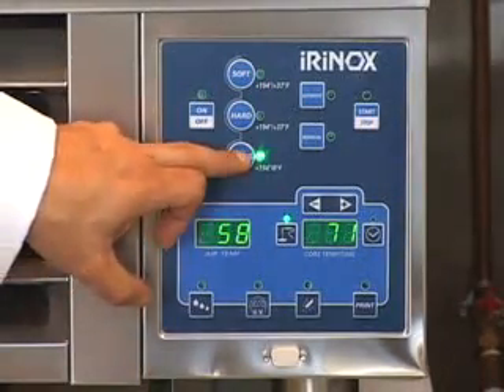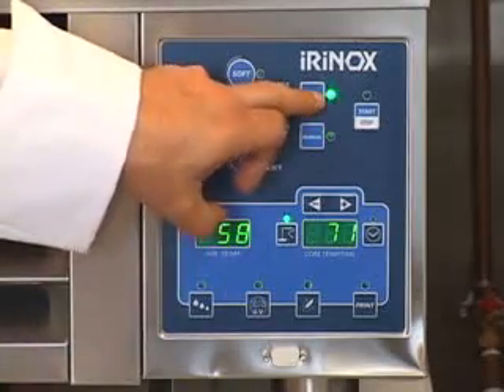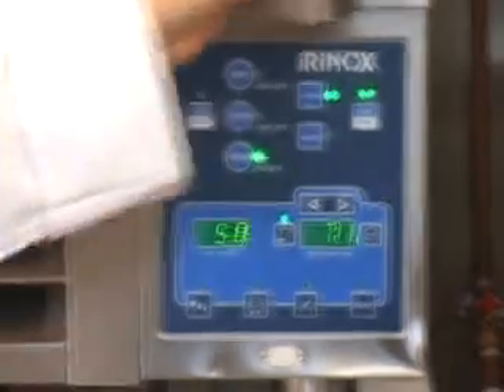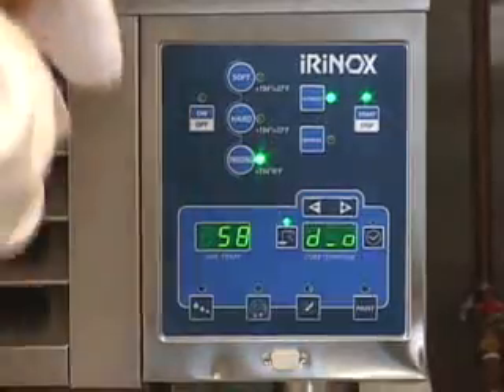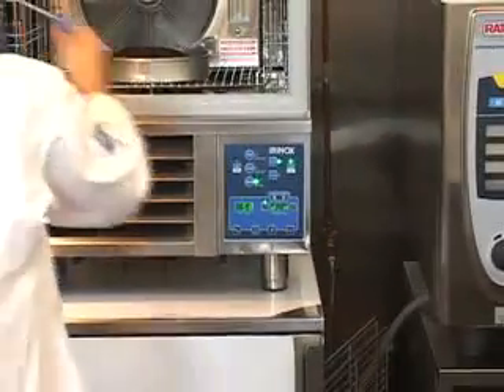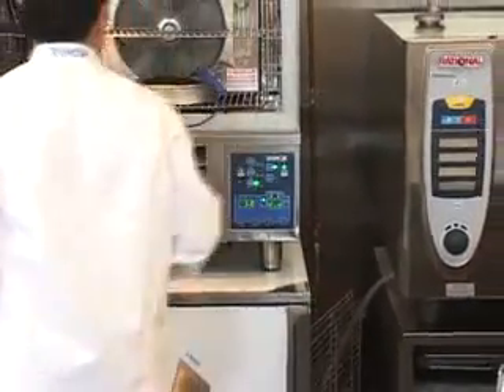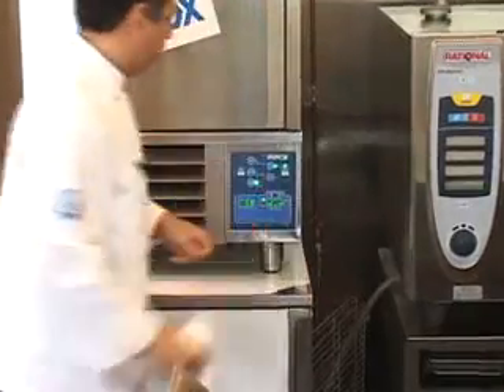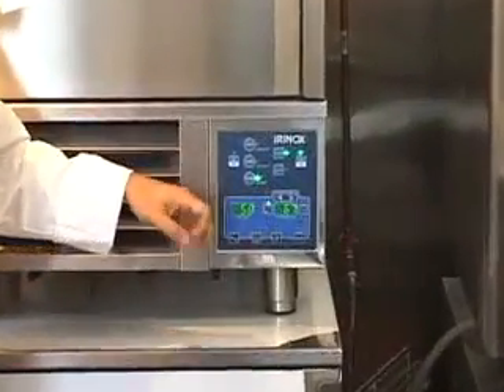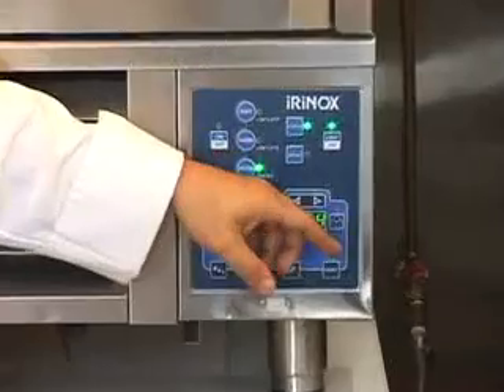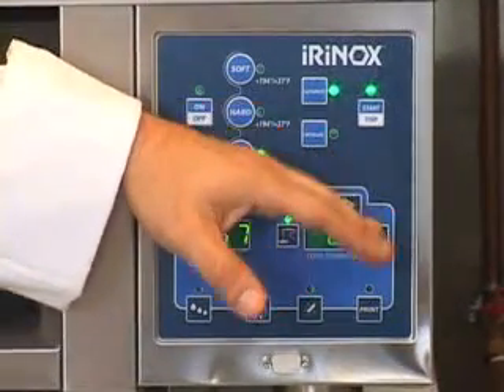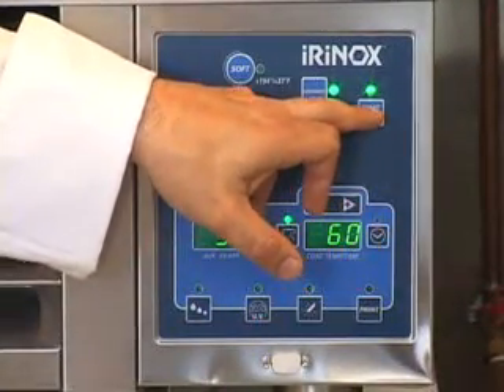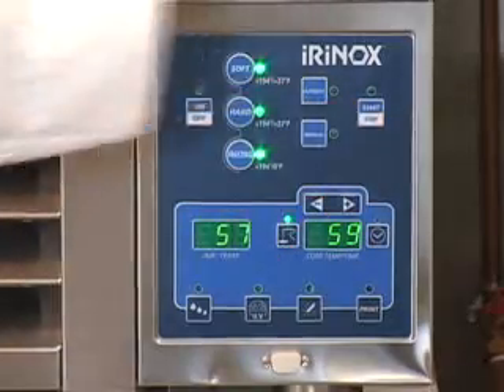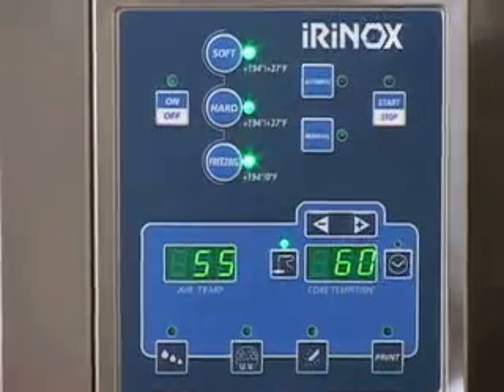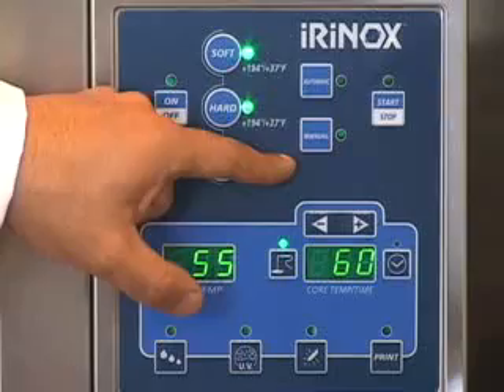Again, I select the shock freeze cycle, I select automatic, and I select start. I now put the item into the shock freezer, I insert the probe into the center, and I close the door. The unit will now run automatically until the core temperature gets to 0 degrees, in which case it'll then go into hold until I come over and I stop the unit. I'm now going to demonstrate the manual mode.